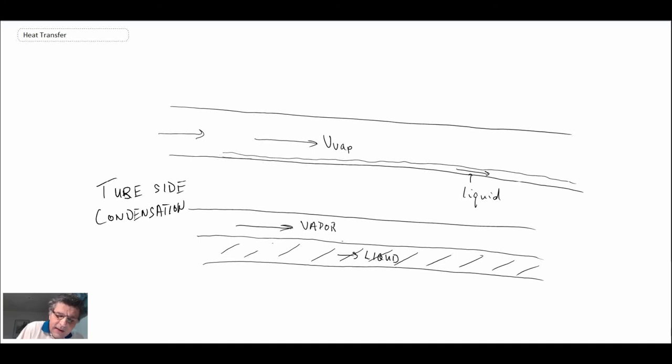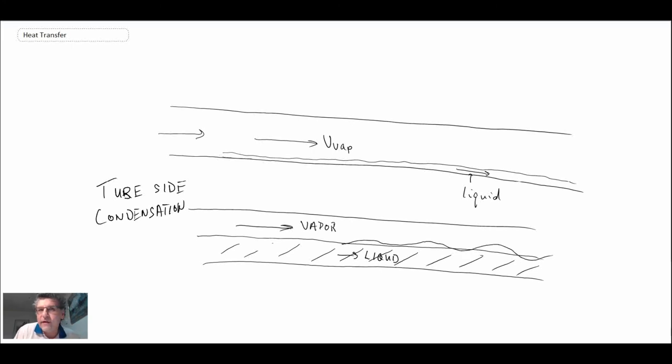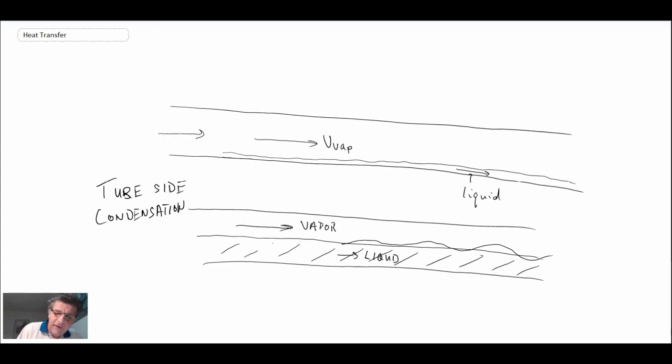You need to be careful because what can happen is if the vapor velocity is high with respect to the liquid velocity, you can actually get instability waves that start to form. That can transition into slug flow and it could cause a very high pressure drop. Multi-phase flow physics can be rather complicated.